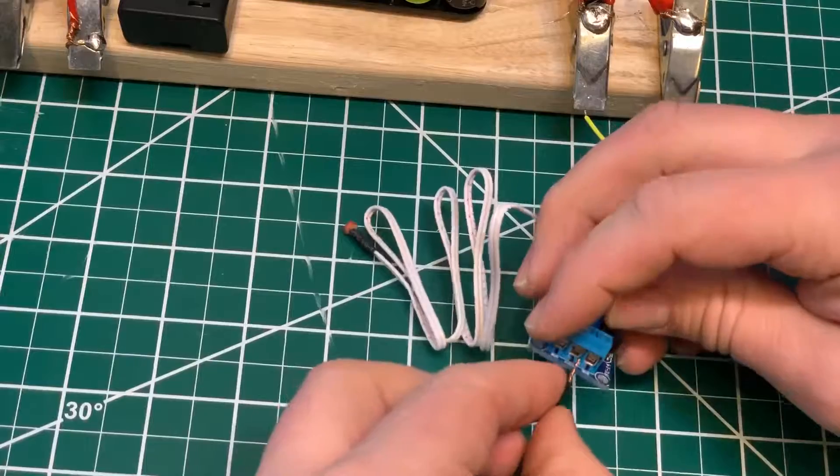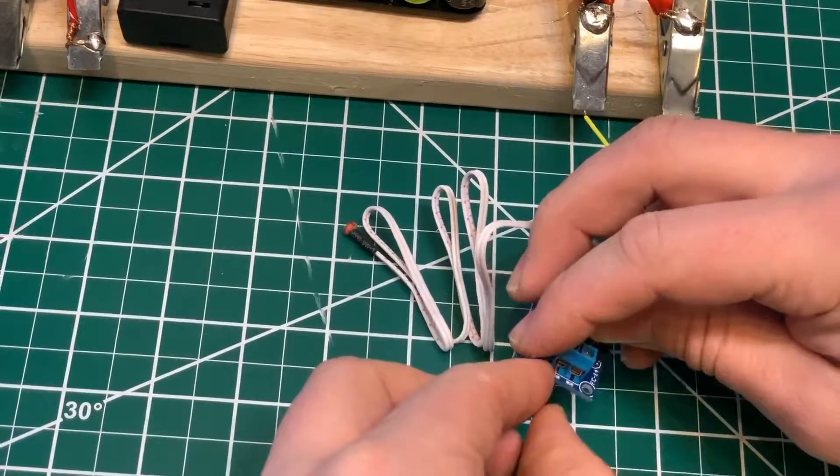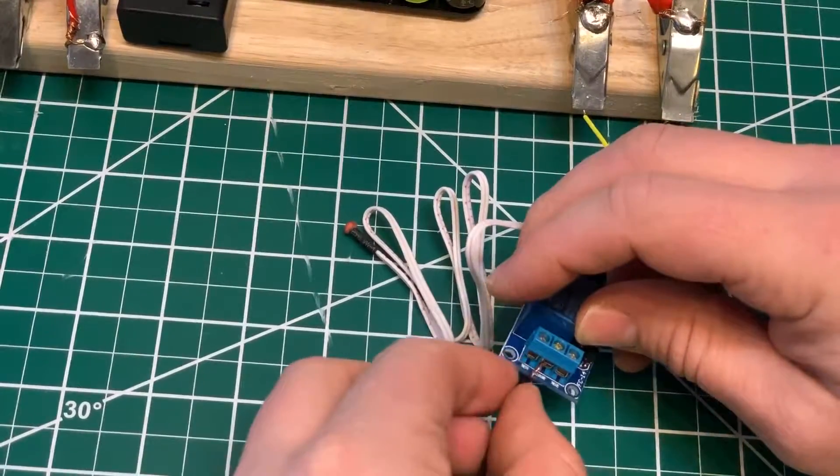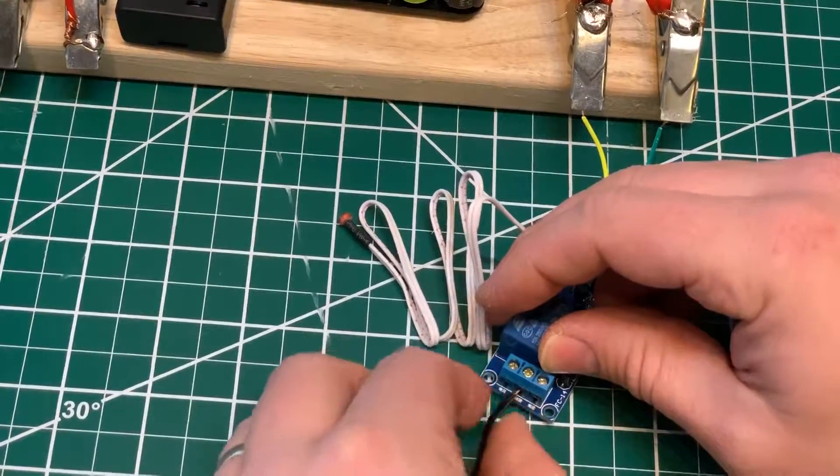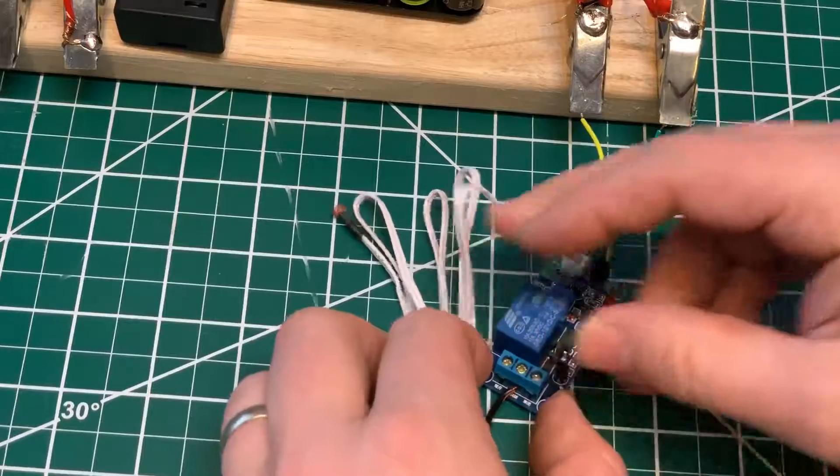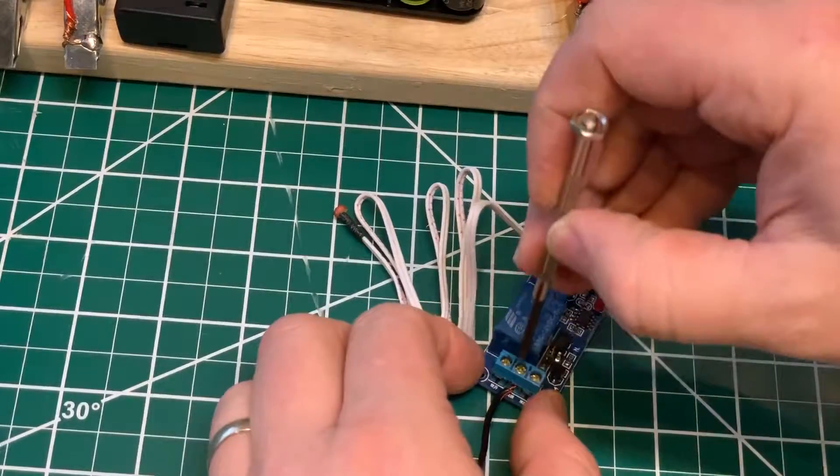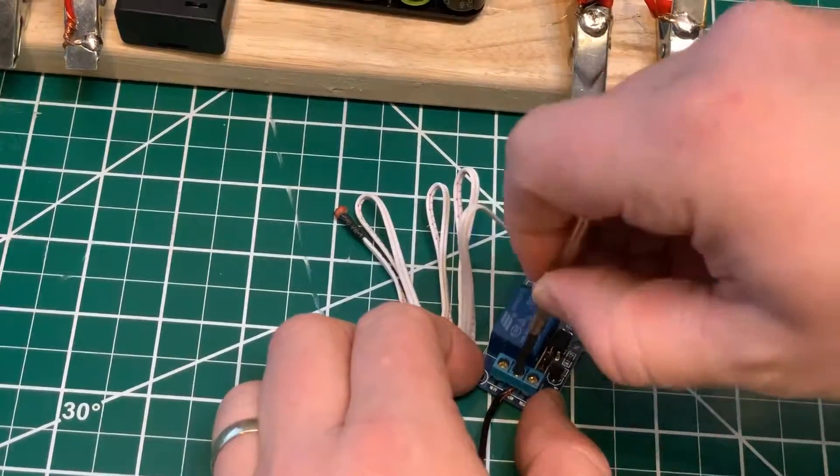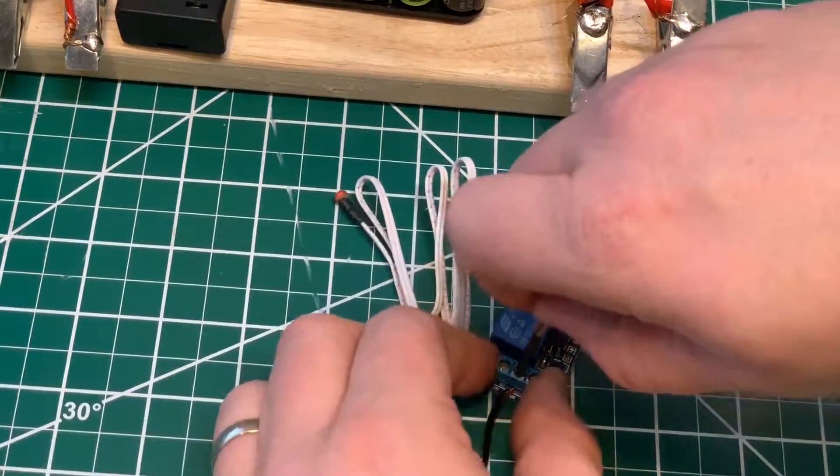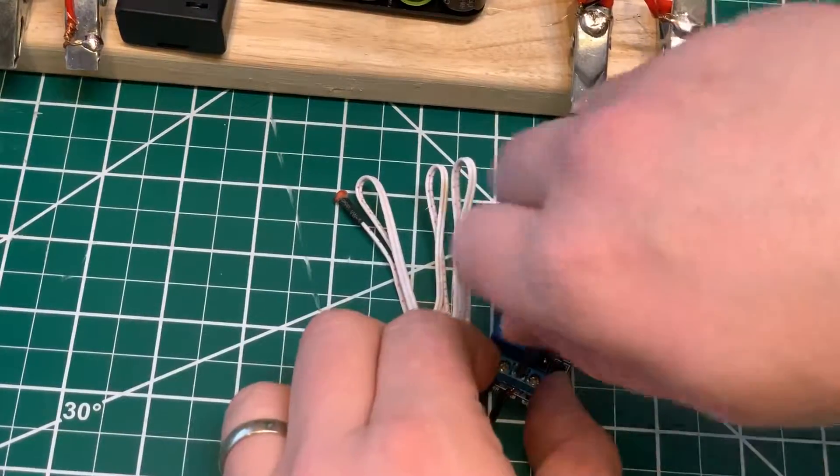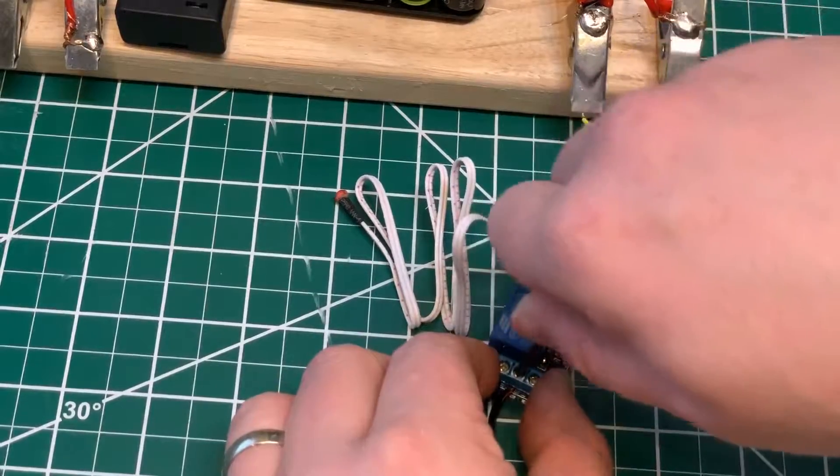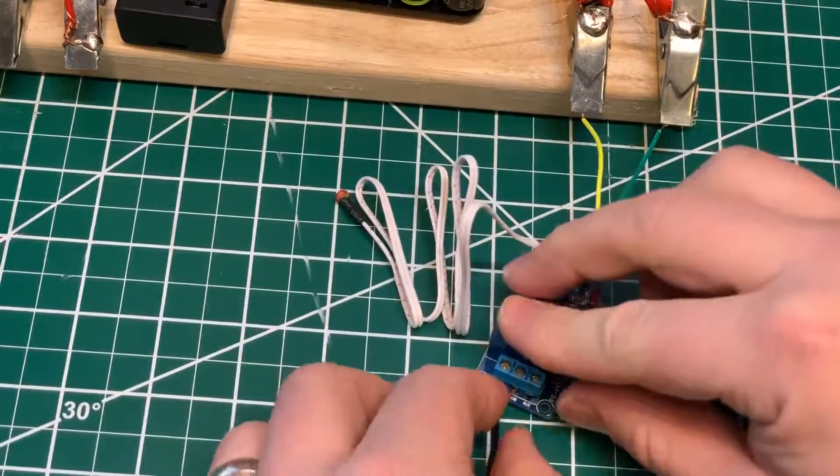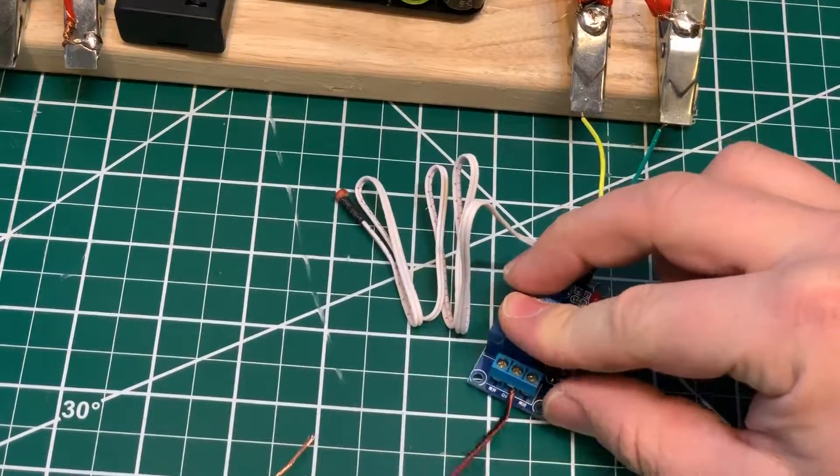So the middle one is common, and that means you leave this wire in and then you can move the other one from left to right to make it normally closed or normally open.